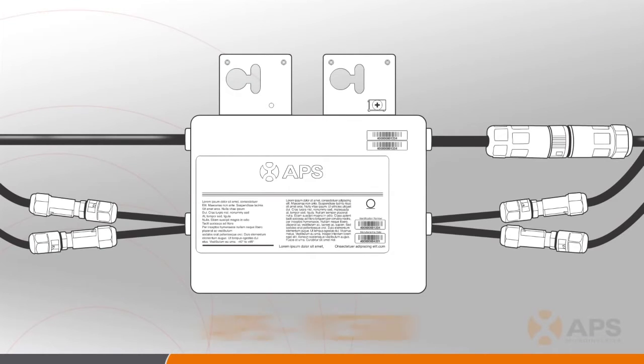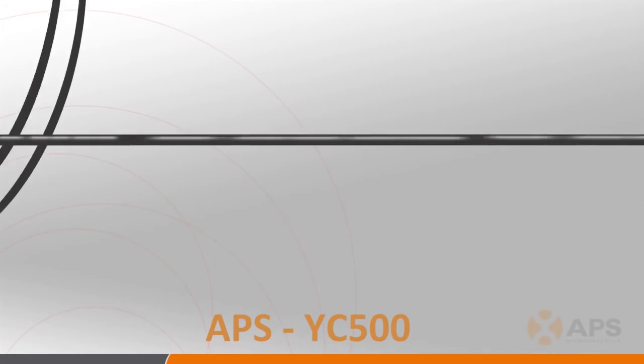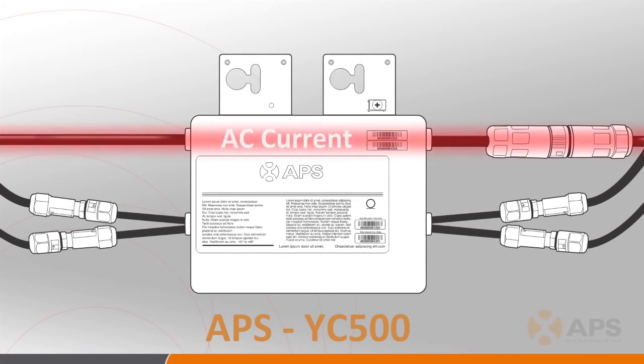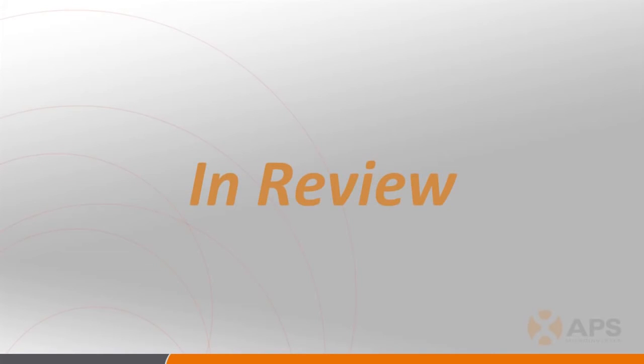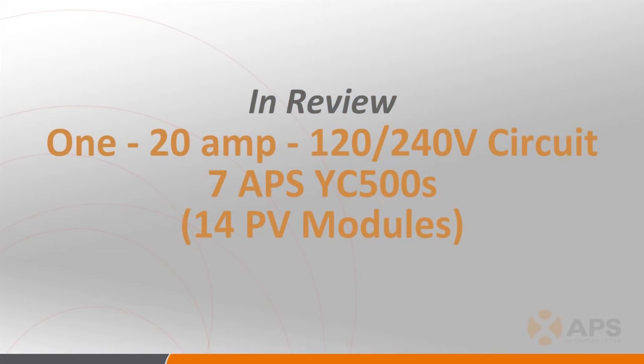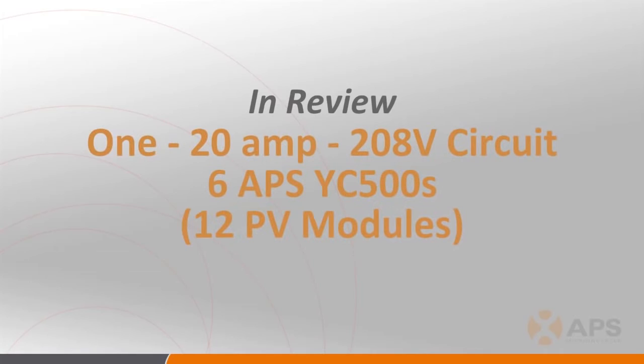Here is a picture of the YC500 showing its associated cabling. It's important to note that the YC500 does not use a trunk cable for AC distribution, but rather are daisy-chained together in series. The top cables in the photo are the AC cables, and the bottom four — two on each side of the inverter — are the DC input cables. As review, the maximum number of units per 120-240 volt, 20-amp circuit is 7, or a total of 14 PV modules, and the maximum number of units per a 208-volt, 20-amp circuit is 6, or a total of 12 PV modules.